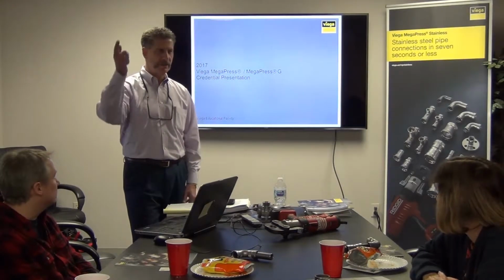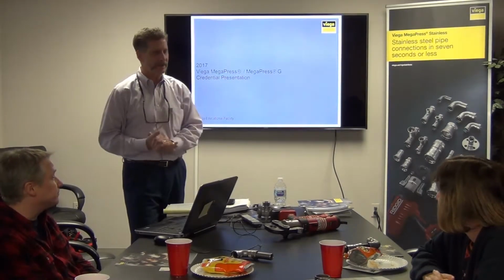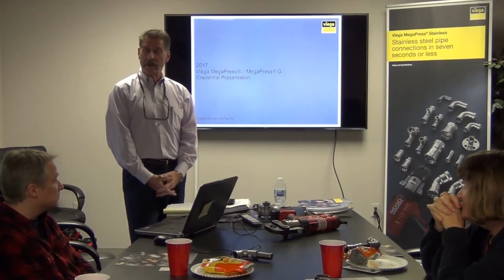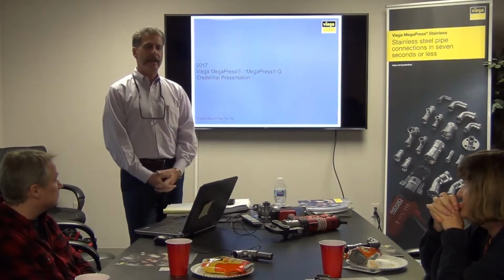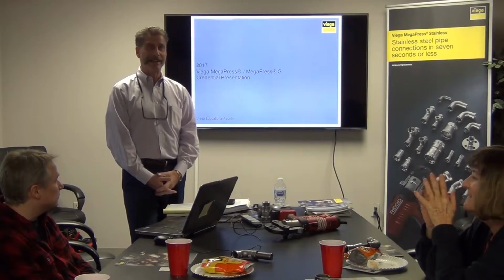Case in point, I was up at State College last week doing a lunch and learn for their whole renovation department. We had 12 techs in there and a couple of engineers, and they told us about an incident that happened only 2 years ago using a competitor's ProPress type, meaning in copper, and it held for 2 years before it finally let go.